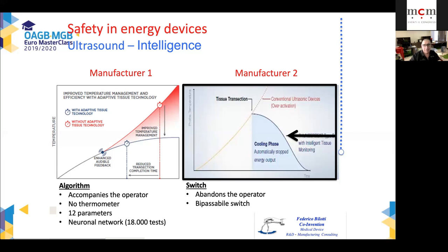What I say is that the instrument is not as safe because it stops the electrical discharge, but it does it at its own decision when the electricity reaches a certain demand. And this is as unsafe as if you are driving your car on a highway, reach 120 kilometers per hour, and then you take your safety belts off, and then you want to continue driving. This is unsafe. Same happens to this instrument. When you reach a certain electricity demand, the switch turns off, but you want to continue working. And you have to bypass the safety switch and continue without safety. On the left side instead, you see the ultrasound chart. It shows that beeping alerts you on the fact that the instrument took over and decided when the cutting takes place. And it's faster than if you alone continued applying electricity.